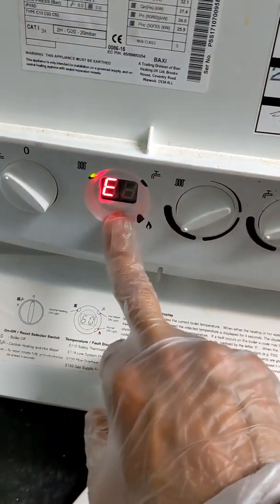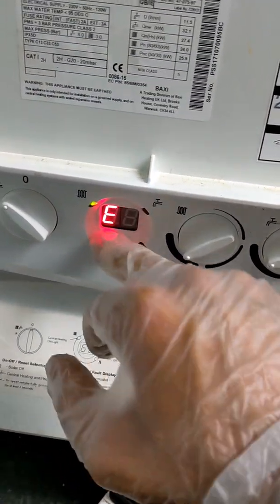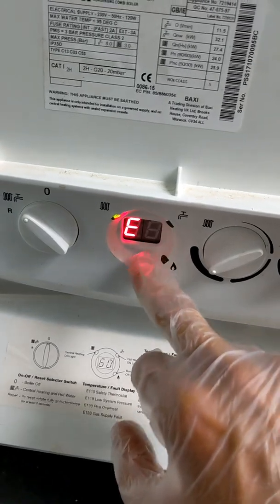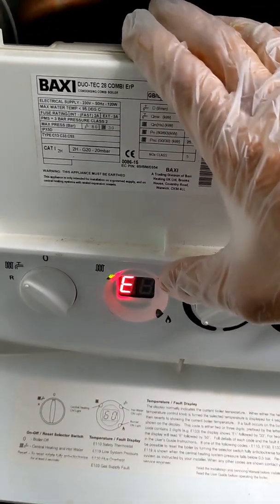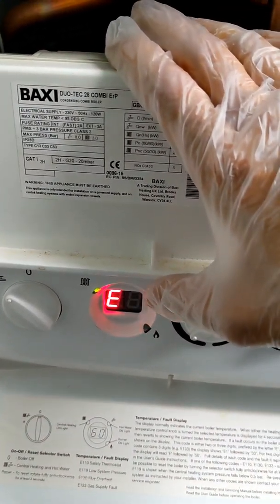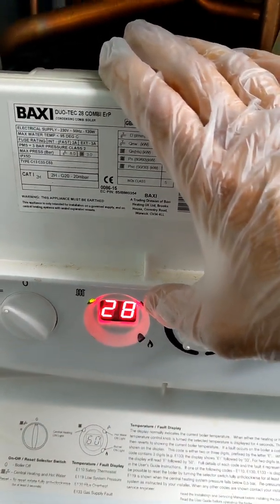Now, E28, although it says flow thermistor when speaking to Baxi tech, it actually means that it could be a fault related to any component. So the first thing we check is the X401 connection on the PCB to see if we've got continuity across it, which we didn't.